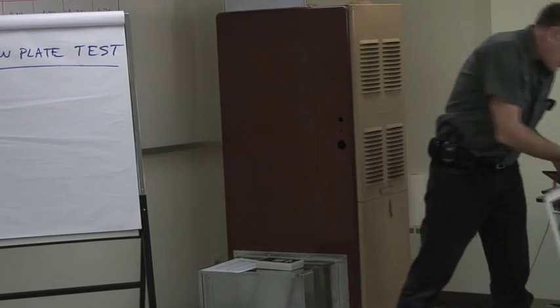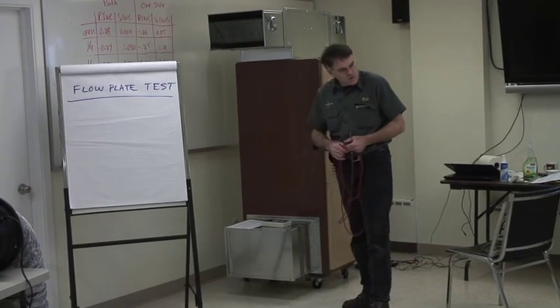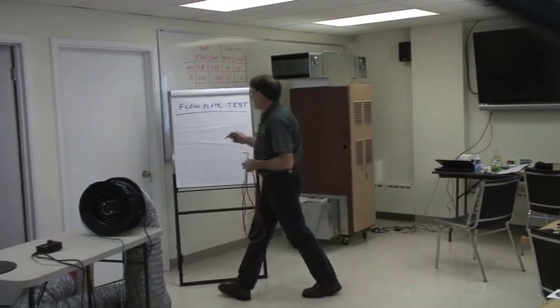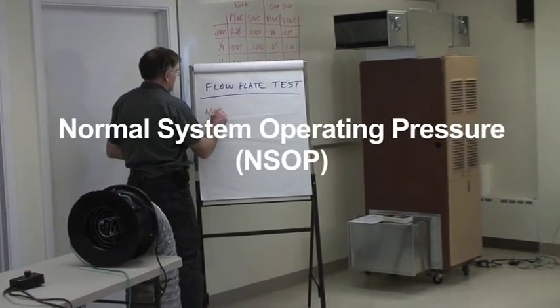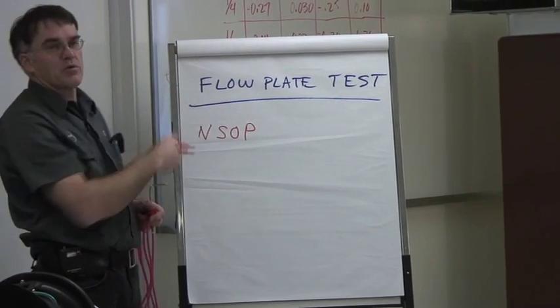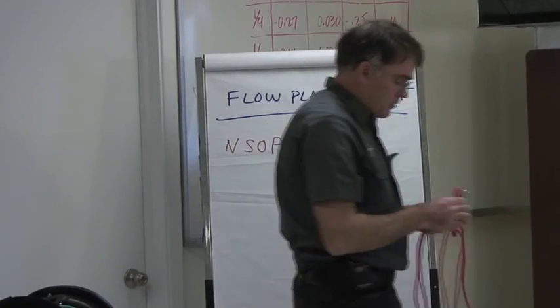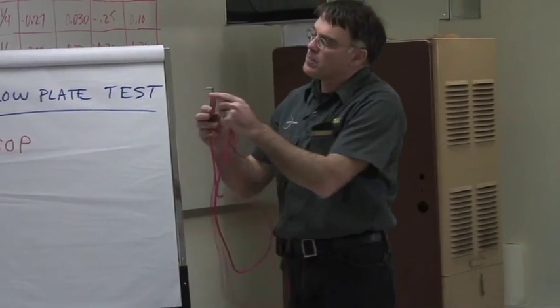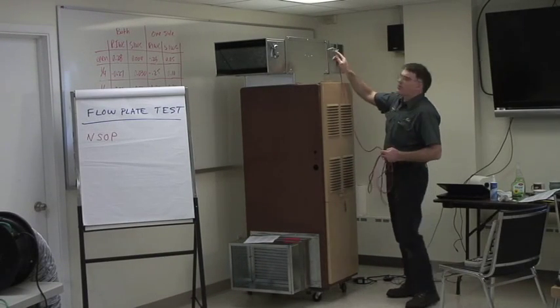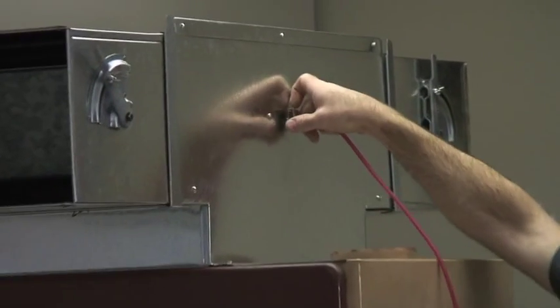There's a couple parts to this test. The first part is to come up with what we call the normal system operating pressure. We usually measure on the supply side, you could also call it supply operating pressure. For that purpose we'll use our static pressure tap. It has little holes on the side, so we're going to place our static pressure tap up in our supply plenum to get a normal system operating pressure.